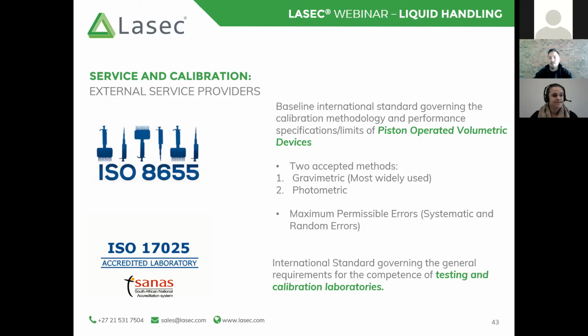So what SANAS ensures is that the laboratory that is carrying out the calibration has all the equipment certified to very strict criteria, and that the operators are competent in actually calibrating and pipetting, or in calibrating and testing your devices. It does not dictate how a calibration is to be carried out. So you will find that even if a certificate is SANAS certified or accredited, this is a lab's accreditation, the standard to which the pipette calibration is carried out will still be stated as ISO 8655.